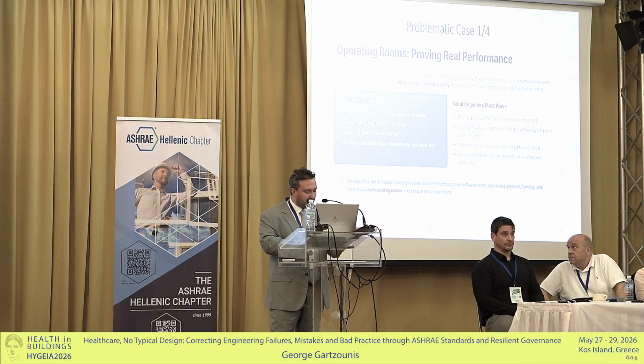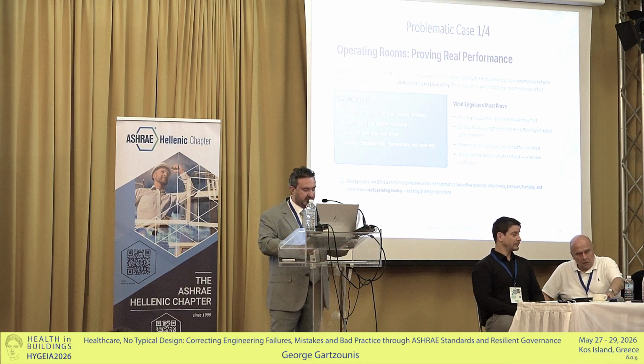Operating rooms are the strongest open case because doctors understand the consequences immediately. An operating room can look modern and still fail if pressure, airflow direction, temperature, humidity, filtration, door discipline and controls do not work properly. High air changes per hour won't save the situation. That is not safety.